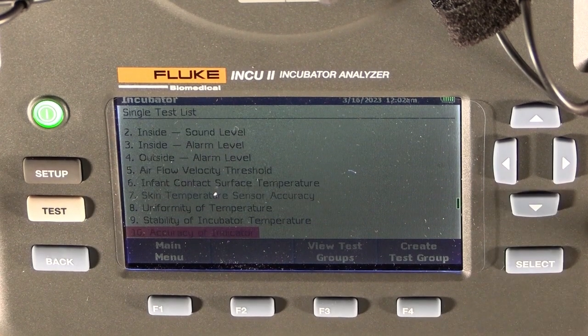Step number 10, the accuracy of the indicator. When we refer to the indicator, we are talking about the LCD or LED readout of your incubator that shows you the temperature measured by the incubator, and that we are comparing to the T5 temperature sensor inside the incubator. Also, we need to set it up and wait for the machine to reach stability. Then over a selected period, be it half an hour or an hour and a half, we measure the stability and the accuracy of those two readings and we compare them.